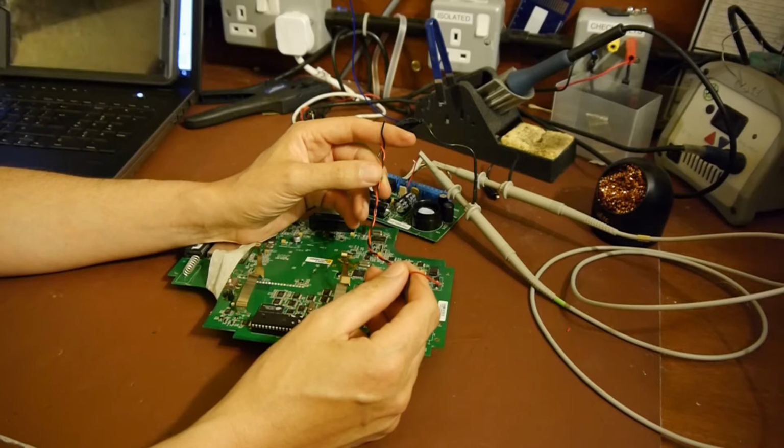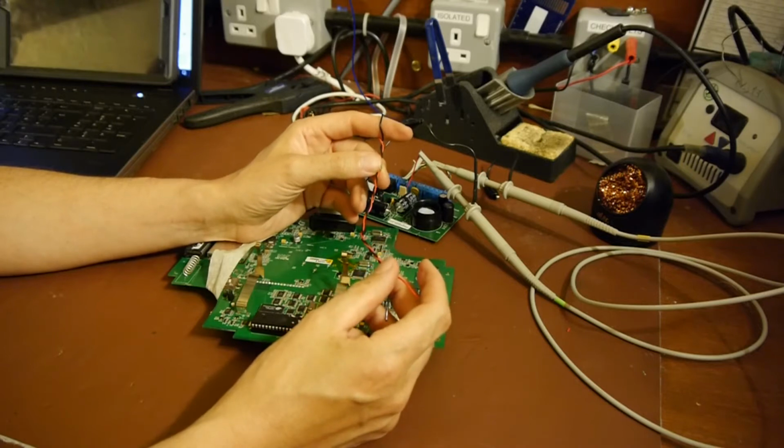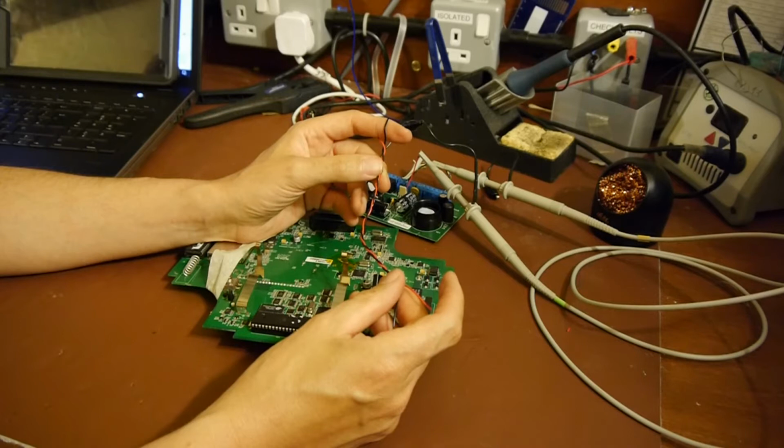Now I realise I haven't given a particularly in-depth discussion about 485, but all you really need to know is that it's very similar to RS-232. But the problem with RS-232 is it can only go a few tens of feet, and it's designed for connecting computers together locally. But the 485 network has the great advantage that it will go up to 4,000 feet.